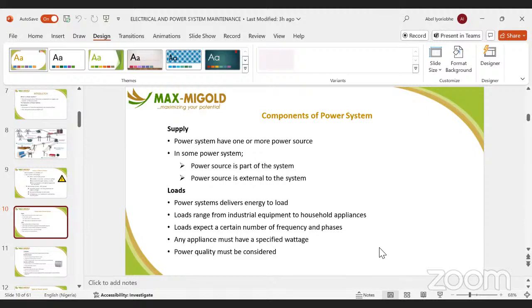That's what we call load analysis. You determine the type of load, whether three-phase or single-phase, then pull them together. This will help you distribute your power supply so you have a balanced load on your generator or source of power. If your load is imbalanced, if a phase is overloaded, it will affect your alternator and your transformer, because the power system is stressed beyond what it can withstand.